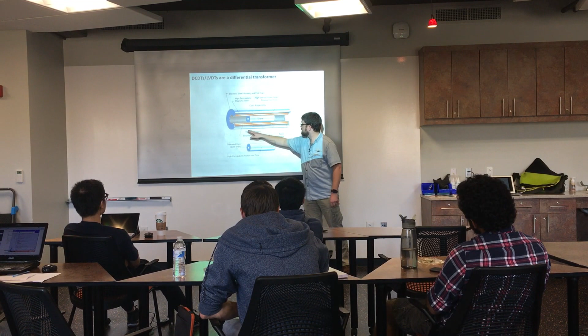The idea is we have a core that slides through the assembly, and that's what we're measuring the displacement of. In the outer part of the transducer there are two windings, it's a transformer, with a primary winding in the center and secondary windings on either side. As we move the core through, we change the output of the transducer.